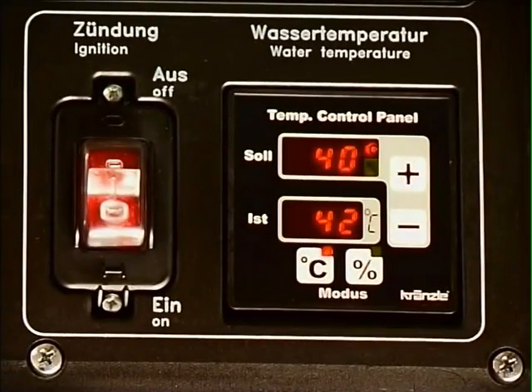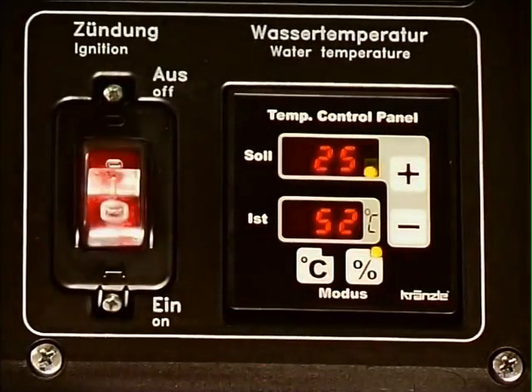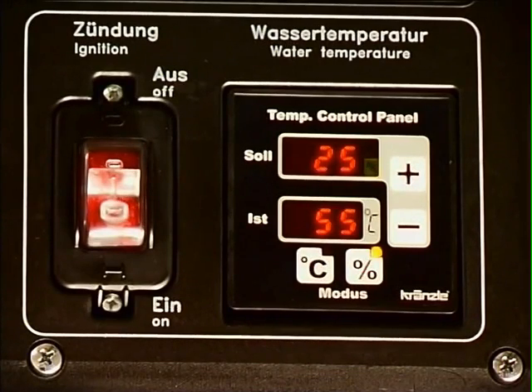Up to now, the thermostat has only indicated target and actual temperature. During some operations, it takes too long after cooling for the desired temperature to be reached again. The new percentage mode elegantly solves this problem. The operator no longer only inputs the desired temperature, but can also input the heating time in percent. Thus, the temperature can be kept constant in a very narrow range. There is more detailed information in your operating instructions.